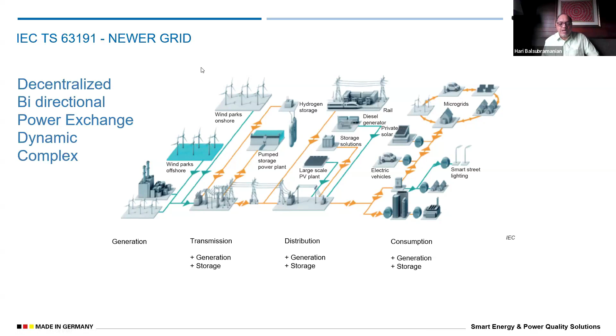In the complex world of electricity, from generation to consumption, there are many issues: fluctuating power infeeds, change in energy flow direction, sources of disturbances measured at PCC, and determining who is causing harmonics in the system. Decrease in short circuit capacity of the power system is very important, because as the system goes dynamic, the short circuit capacity changes dynamically throughout the network—at the customer's input, the utility's input, or the transmission side—due to varying energy and different directions of energy flow.